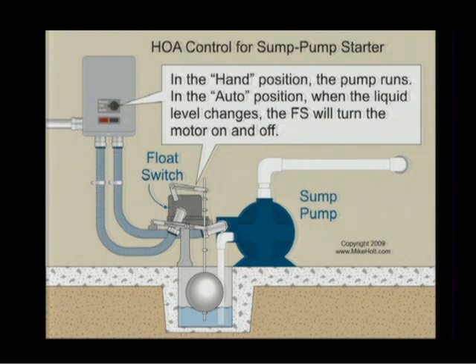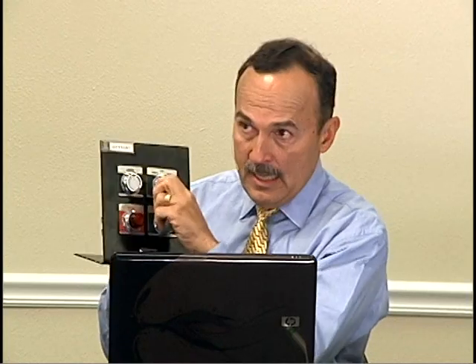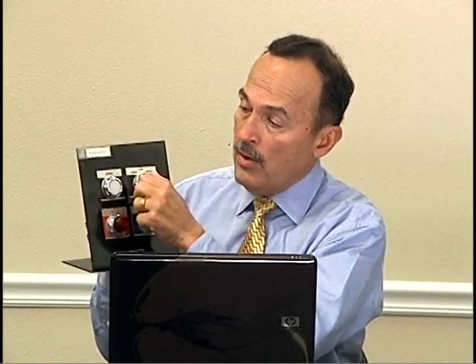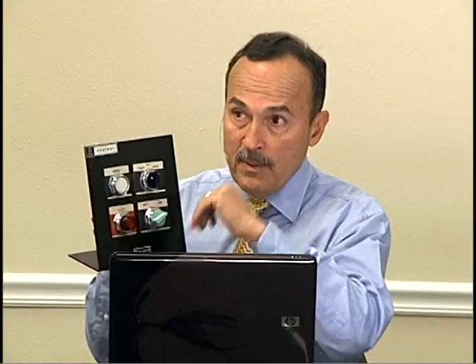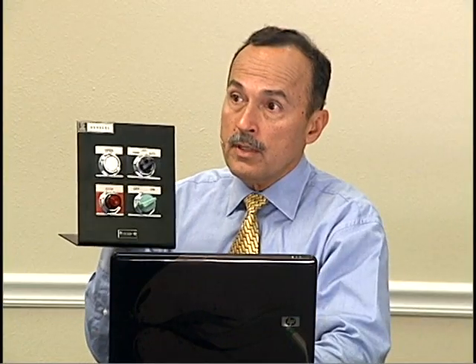Here's an application. All right. Okay, hand, auto, off. In the hand position, the pump runs. Why would they say hand? Does that make any sense? How about just on? Some people will call that manual. That's manual. It's real common on a pump circuit to have a hand-off-auto. That way, for testing, you could turn the motor on. Okay, so if this was called manual, it makes sense to me because it actually has hand-off-auto. Manual means it's manually on, right? I got that. And then it is off, which means there's no contacts being made, and then it's in the auto condition. And in the auto position, you would probably use your float that you have pictured there.